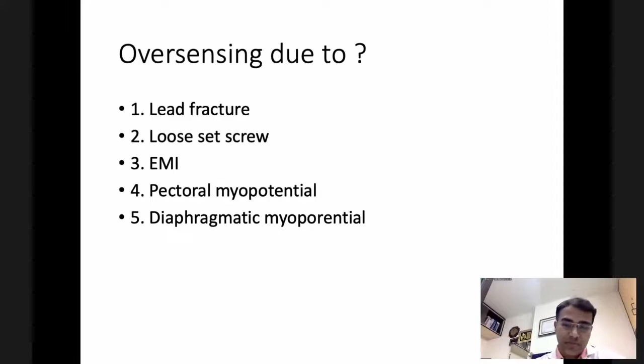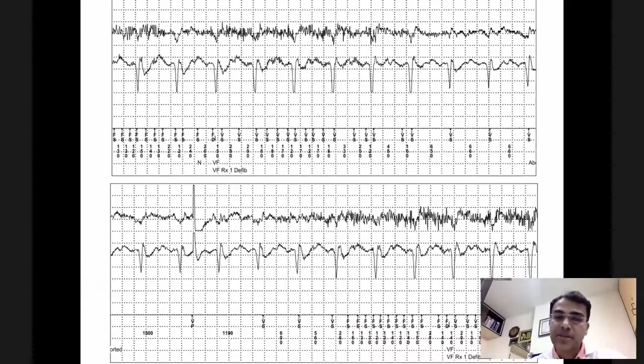But what we felt is that there is a sensing issue: the lead is not sensing, some undersensing is there, oversensing of the noise is there, and the lead was not capturing also. So all sorts of things reflected that there was a lead issue. However, the lead impedances were normal. All the lead impedances, sensing, pacing as well as high voltage impedances were normal. And on the X-ray, what we found was the lead was almost out of the heart.